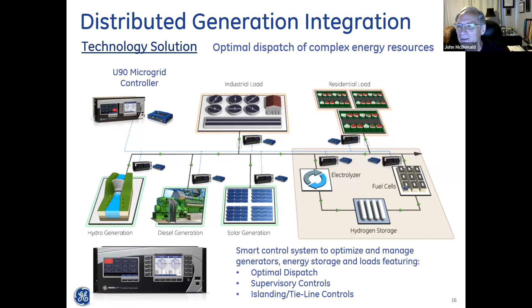So we took a microprocessor-based relay in the upper left here, a U90 protective relay, and added logic to it to become the microgrid controller, okay? We said we need to satisfy the load continuously, but we want to maximize the use of the hydrogen fuel cells, the solar generation, and the hydro generation, and minimize the use of the diesel generation. And these blue boxes here are high-speed communications equipment, so we know what's happening around the grid continuously. Okay.